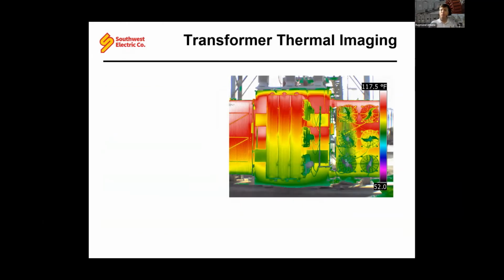Couple that, while you're doing your oil sampling, we also recommend customers do an IR, an infrared scanning of that transformer. It's a simple, easy way to get a good feel of the convection going on within a transformer. Usually you're going to see your hottest temperatures at the top, your coolest temperatures at the bottom. And based on this scale and that 117.5 Fahrenheit temperature, this transformer is operating just perfectly. No problems at all, no hot spots, and everything's cycling through as it should.